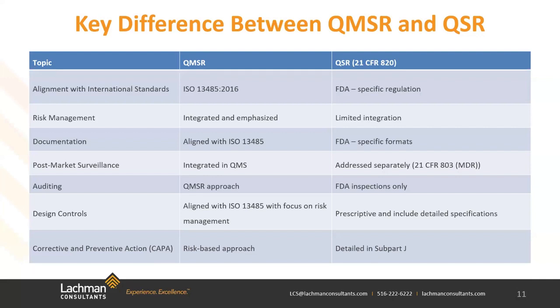Now, as for audits, this is a big one, and I know a lot of people will probably have questions with regards to this: FDA will not consider or accept ISO 13485 certificates, nor will their inspection result in issuance of a certificate of conformity to ISO 13485. This is due to other FDA medical device requirements that they need to ensure companies are meeting, and these are 21 CFR parts 803, which, as I had mentioned, is the medical device reporting, 806, which is medical device reports of corrections and removals, 821, which is medical device tracking requirements, and then 830, which is the unique device identification. Those need to be audited. So that's something that's not going to change.